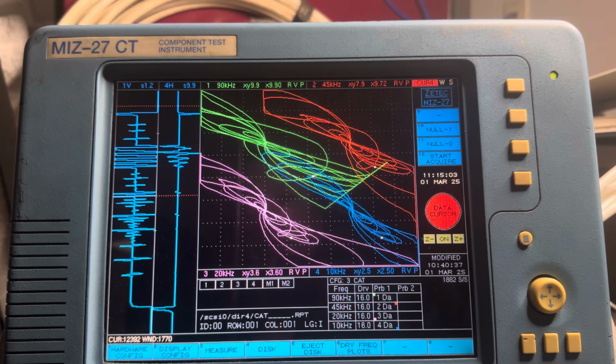Now, I'm not talking about a surface breaking flaw that grows deeper. I'm just saying if you had a small inclusion or a small void, the further you move it down into your material, the more phase lag you'll have away from the probe motion, and the less your signal amplitude will be.